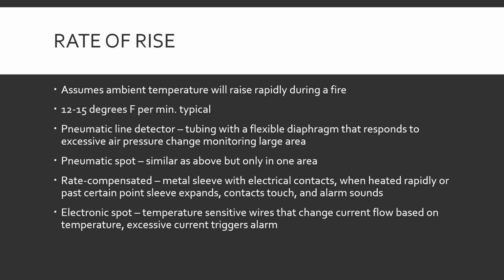Pneumatic line detector. Tubing with a flexible diaphragm that responds to excessive air pressure change, monitoring large areas. Air is a gas, and when gases heat, they expand. Colder air is a little more dense and would fit into a smaller space than warm air. If you've ever had an empty or half-empty bottle of water in your car and it's really cold outside, it's all sucked in, but when you drive with the heat on, over time you can hear the bottle popping and re-expanding because the air in that bottle is warming up and refilling the bottle. That's all that does. The air pressure changes because it's getting hot in a room, the diaphragm flexes, and that sets off the alarm.